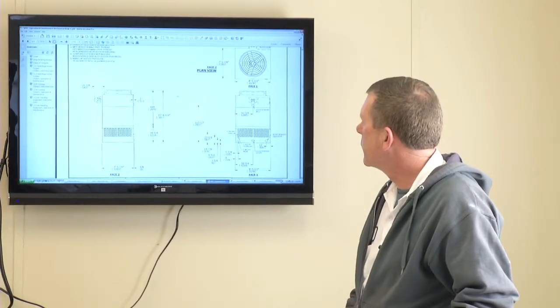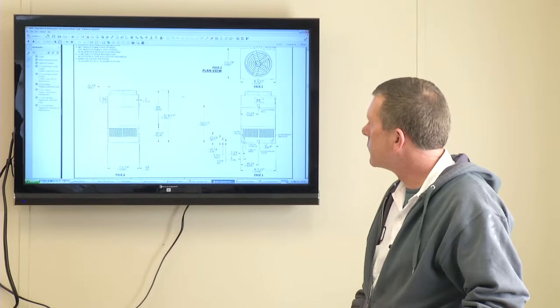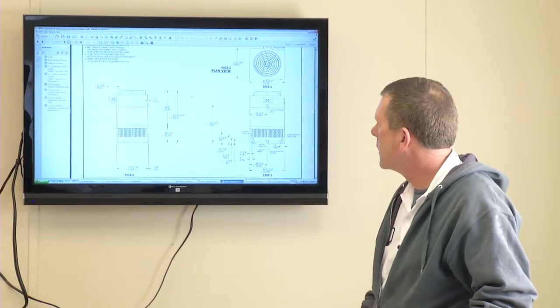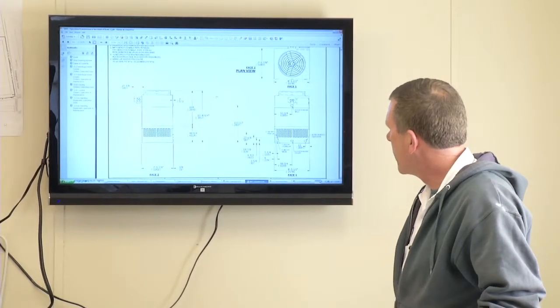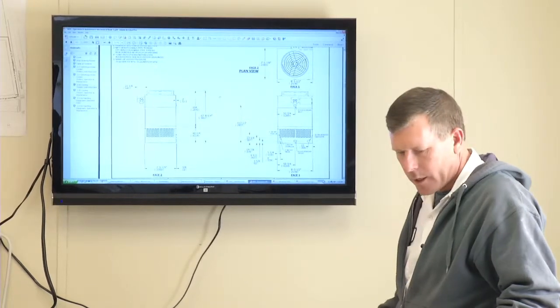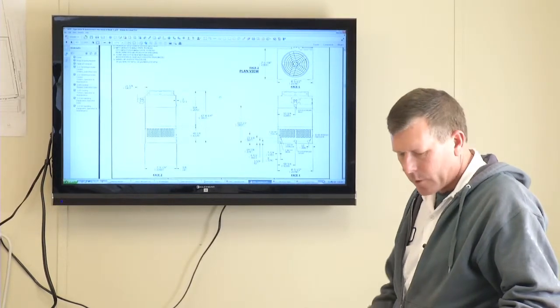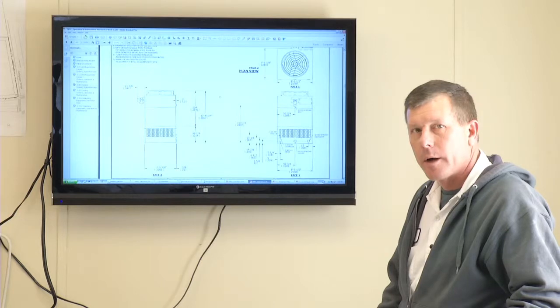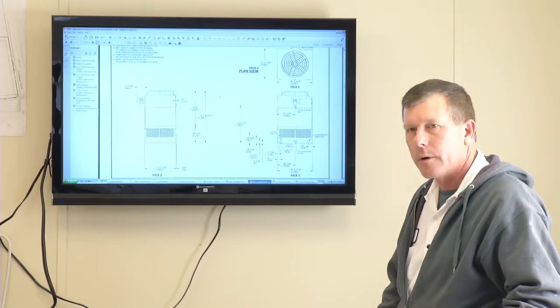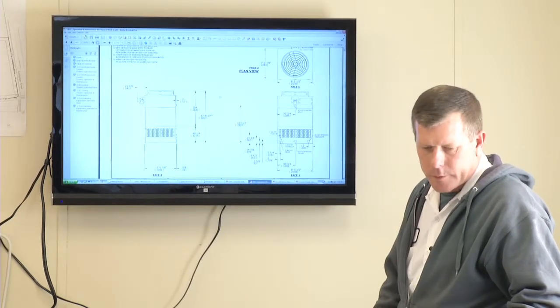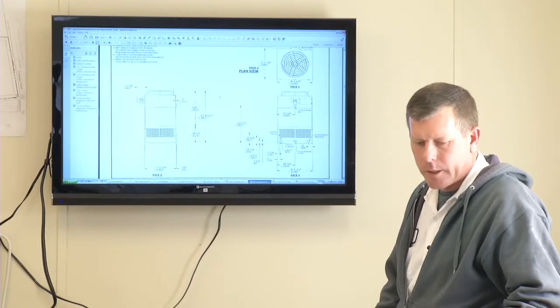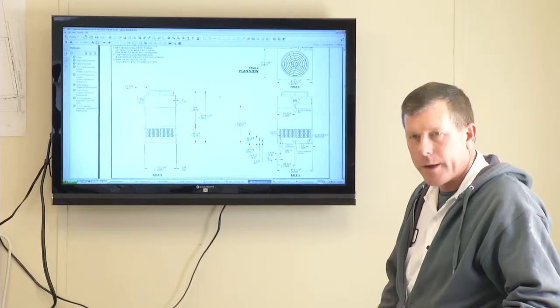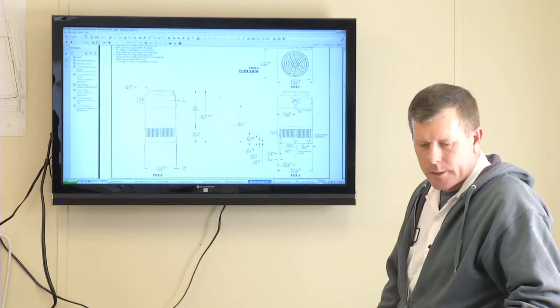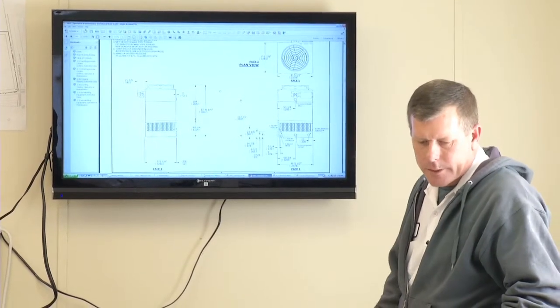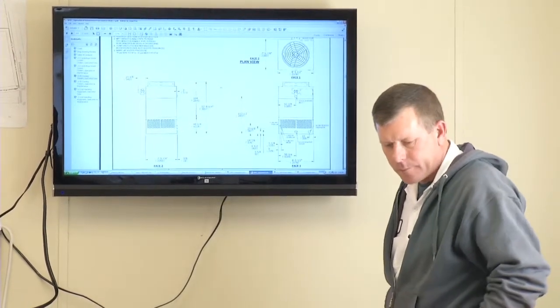Thank you. All right, well, we have our two Evapco cooling towers, two individual, pretty much standalone cooling towers. Like Tony was saying, one can run or the other one can run or both of them can run together. The good thing is one can operate while the other is drained for maintenance. They're designed for entering water at a temperature of 100 degrees, leaving water temperature of 85 max, with a flow rate of 775 GPM in each cell.